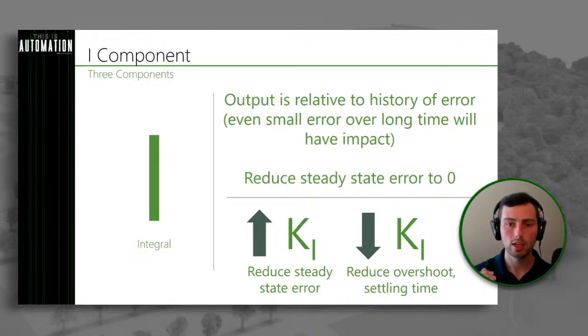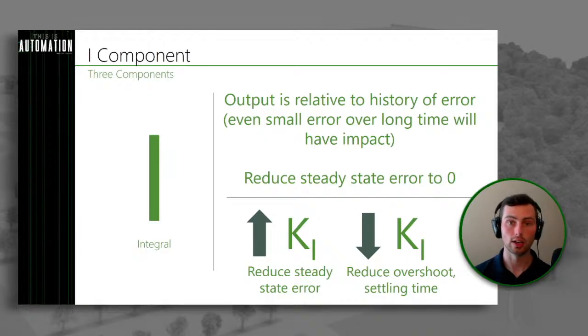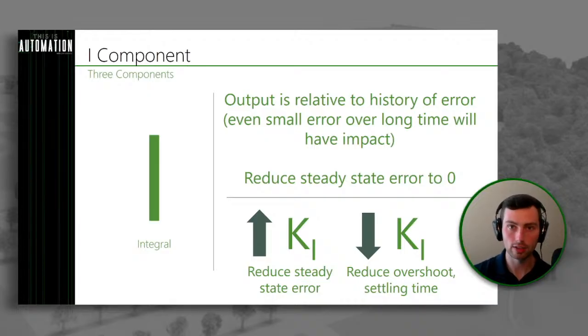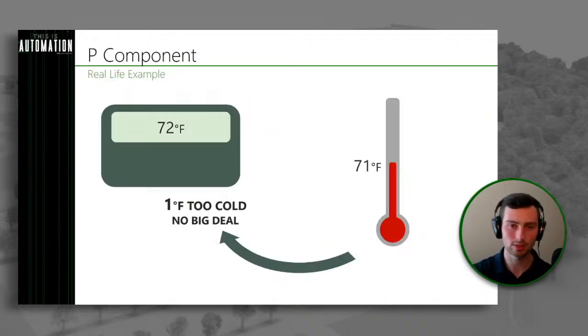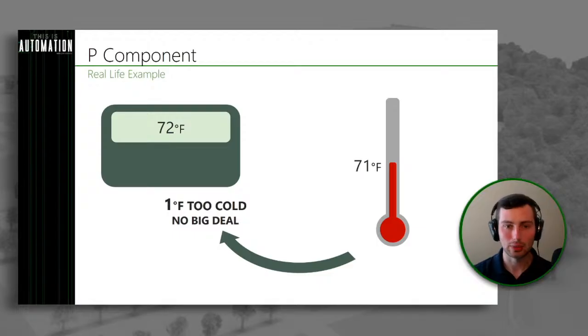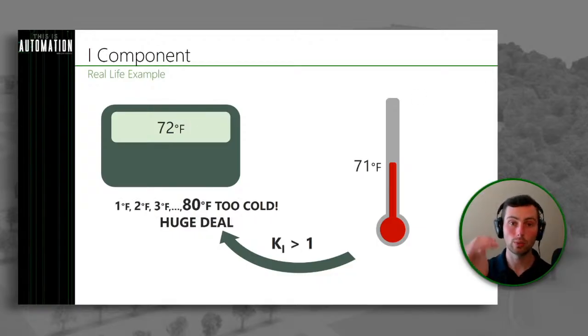If we increase our KI, that's going to reduce our steady state error. But you can have some overshoot introduced by that, and also a longer settling time. As you increase your integral gain, you may get overshoot right around your set point, so in some cases you may want to bring it back down if those phenomena are becoming more prevalent. In our example, the thermostat is set to 72 degrees Fahrenheit and it's actually 71 degrees. If we just have the P component, it's probably not going to do much — it's saying it's one degree too cold, not a big deal.